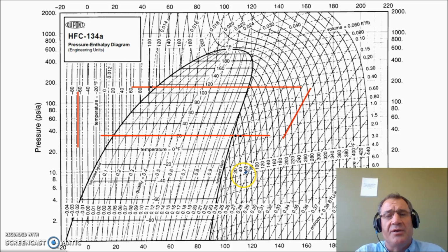And the next two things I can do is anticipate a typical discharge temperature for this system. The temperature on the discharge line is probably going to run around 150 degrees Fahrenheit. So there's 150 right there. And that would represent the temperature on the discharge line 6 inches down the discharge line away from the compressor, knowing that back in the compressor itself, the temperature of the discharge gas is probably about 50 degrees warmer, so that would put us at about 200 degrees Fahrenheit right here.